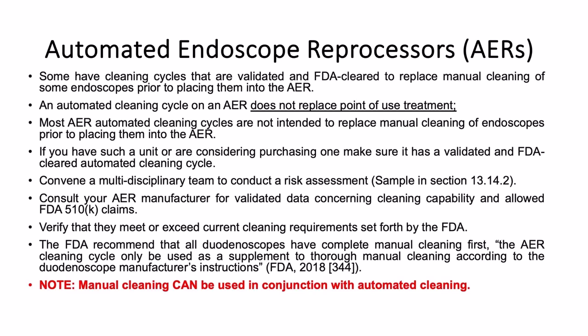If you do, or are considering purchasing one, AAMI recommends that you look to make sure it has a validated and FDA-cleared automated cleaning cycle. And then you might want to get your multidisciplinary team together to conduct a risk assessment about not doing the manual cleaning. And there is a sample in Section 13 of ST91. You should consult the AER manufacturer for their validated data concerning the cleaning capability and FDA 510(k) claims. Verify that they meet or exceed current cleaning requirements set forth by the FDA.